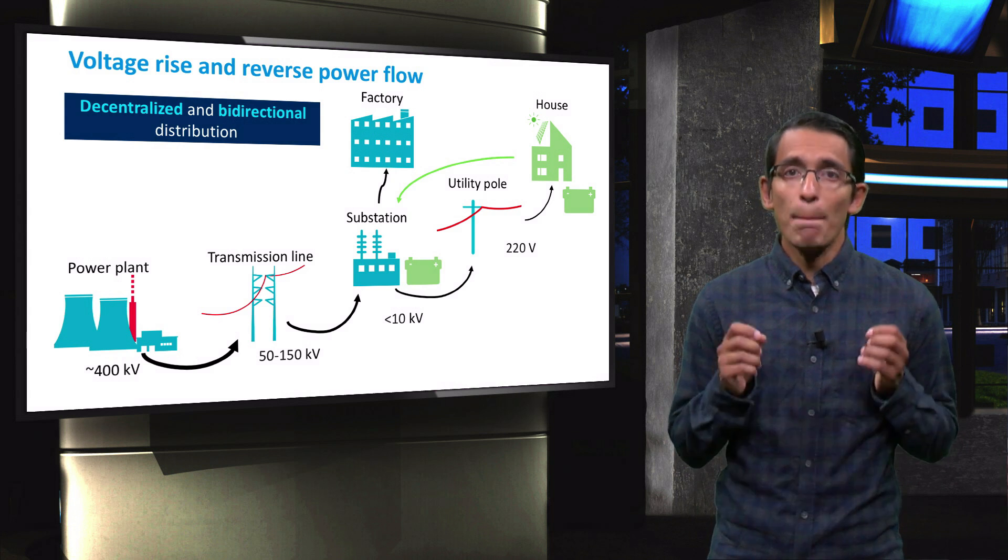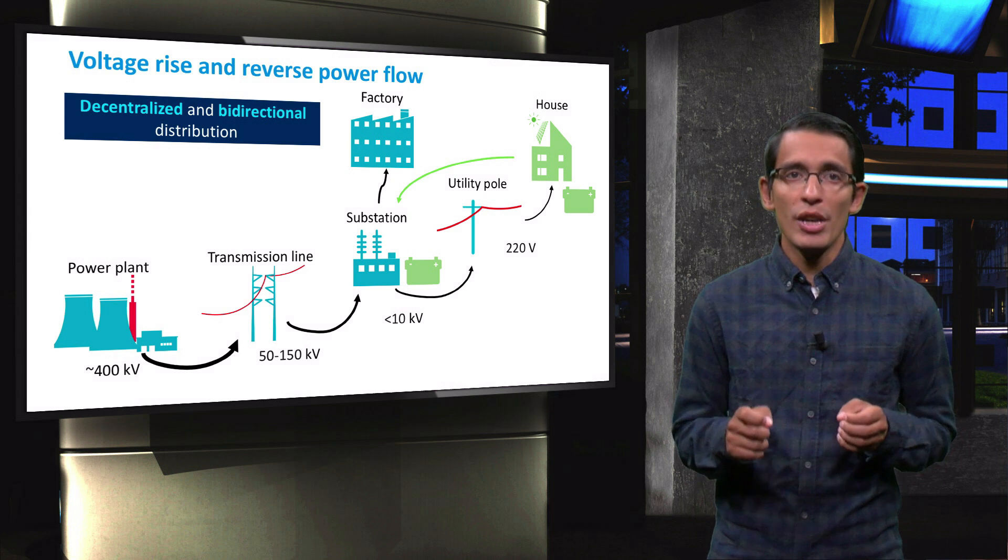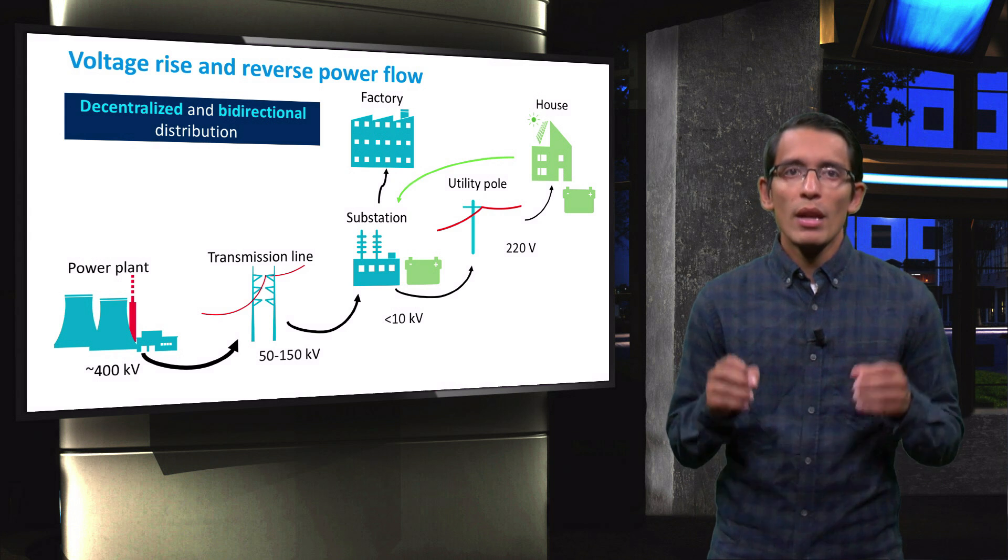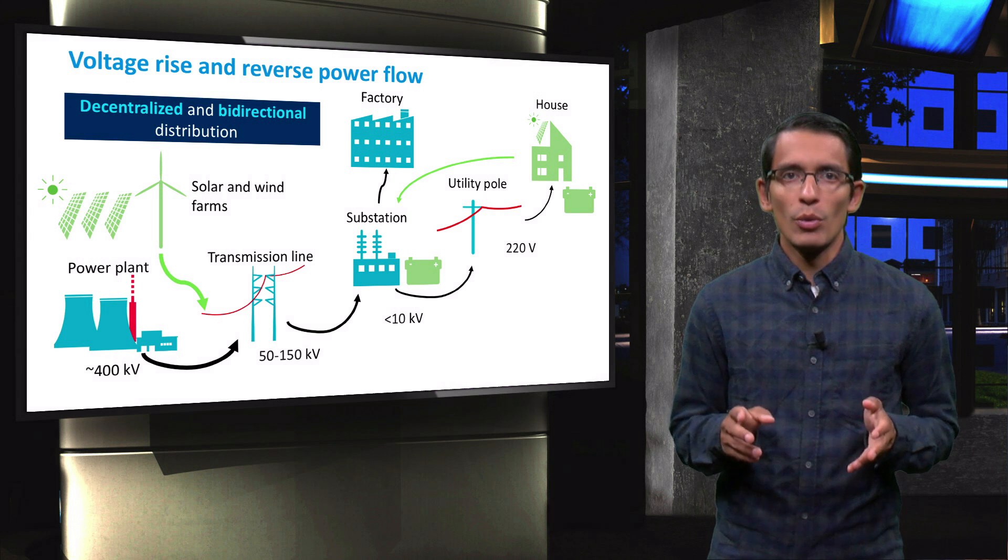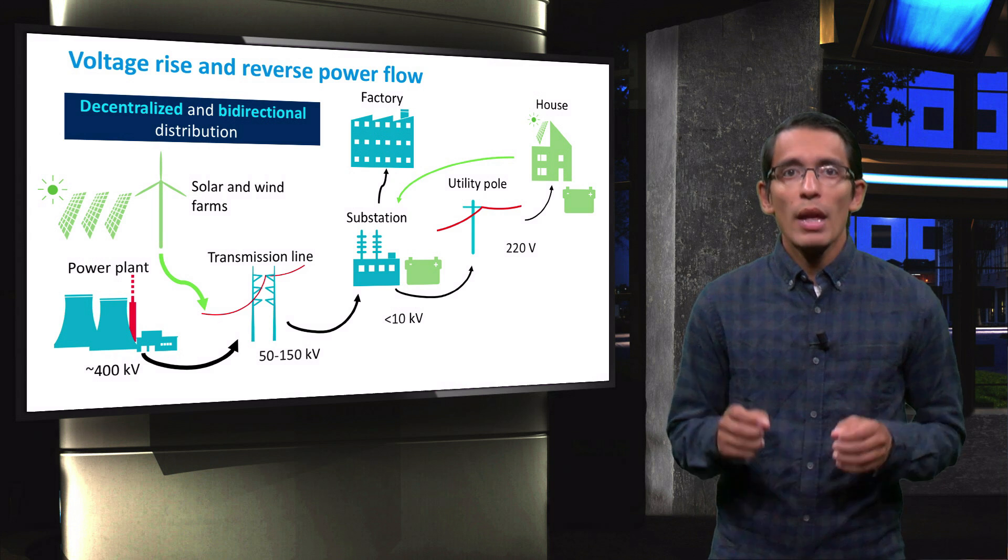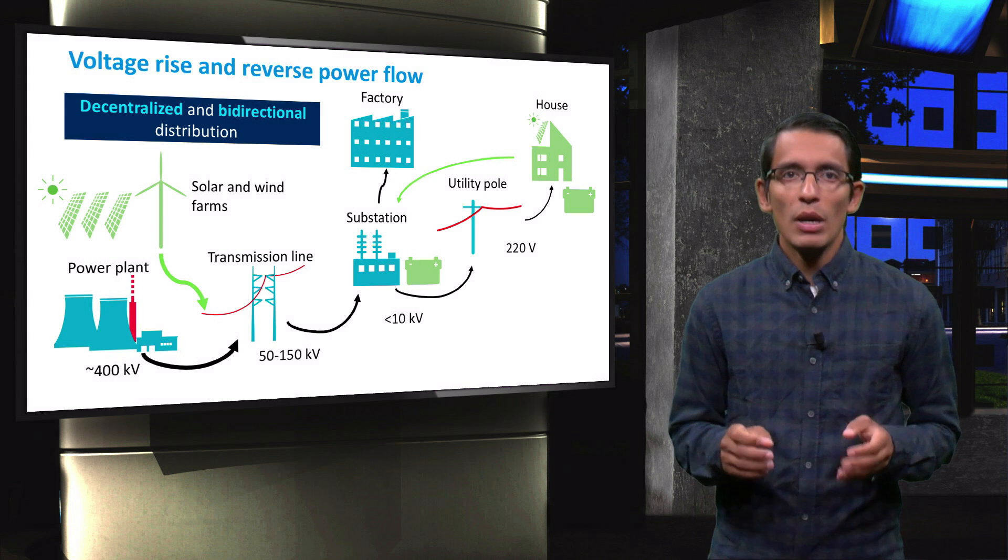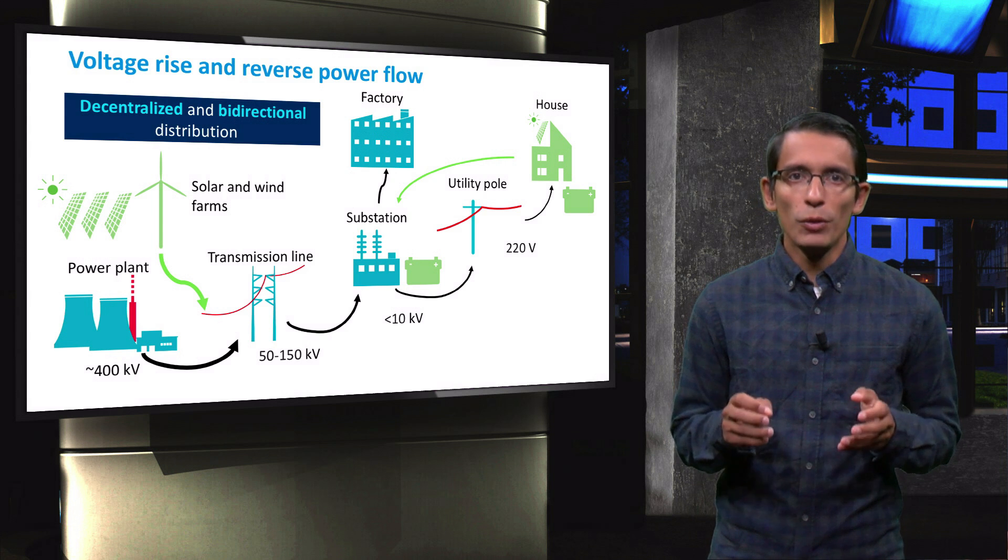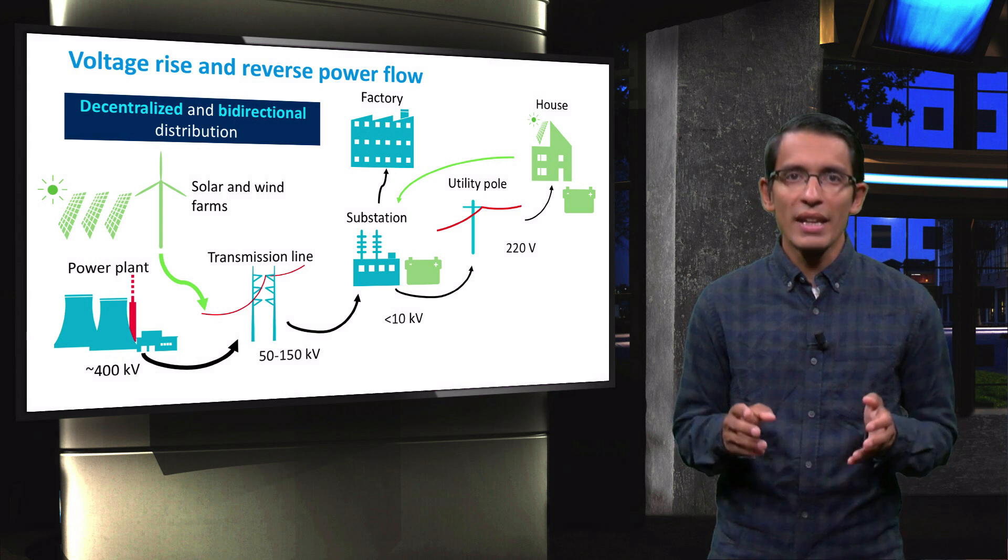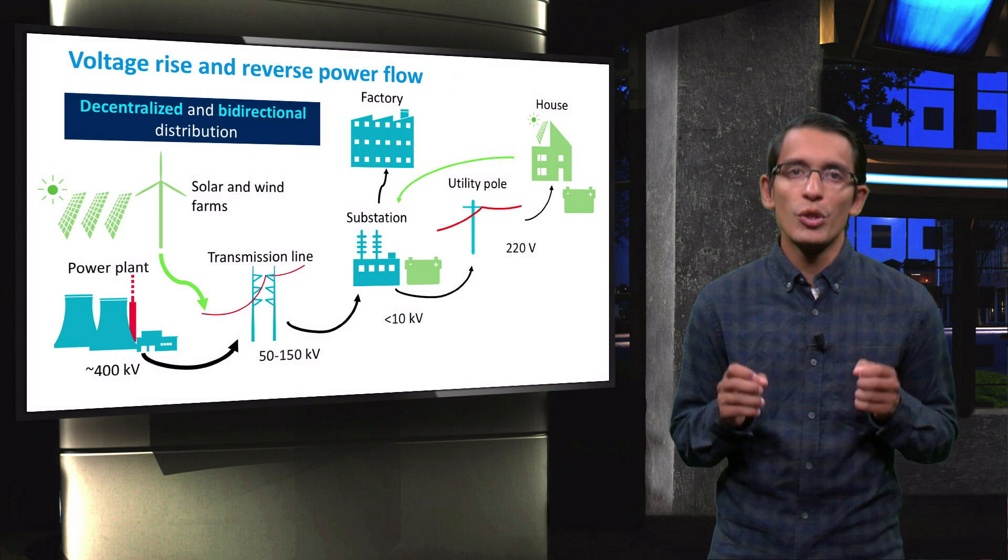Storage systems may be necessary when PV penetration on the grid is high. Bigger solar and wind farms play also a role at the transmission level. In this more complicated scenario, protection devices on the low voltage side of the network are designed to detect and stop upstream current flow towards the transformer.